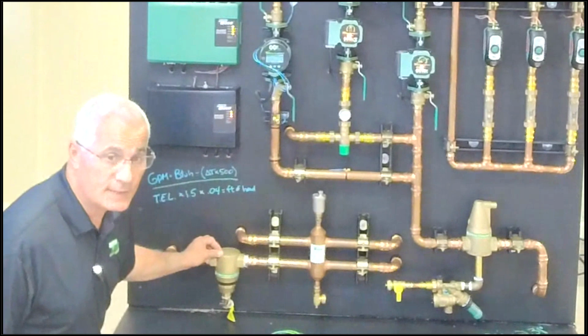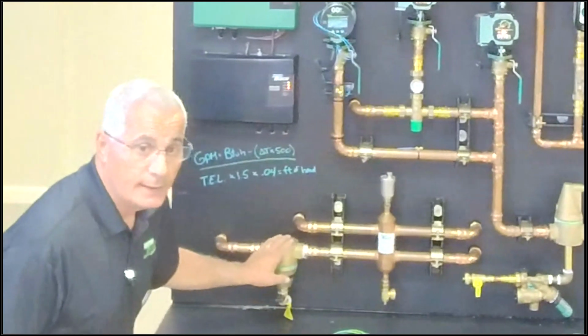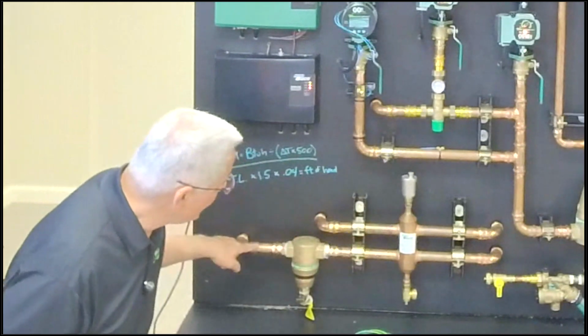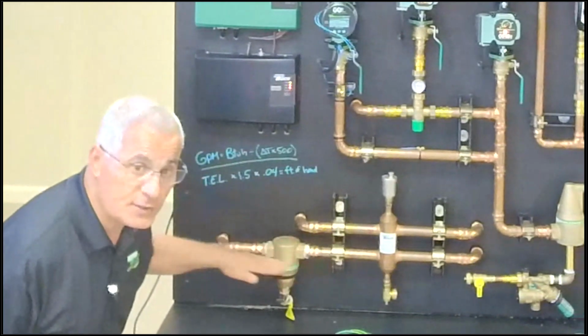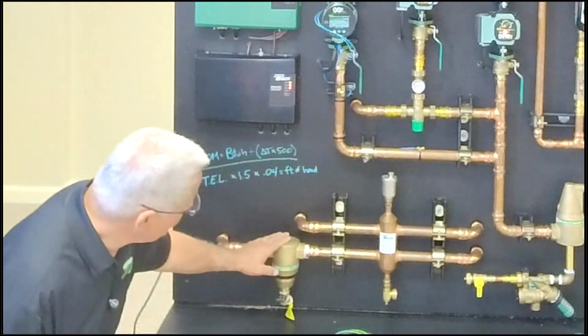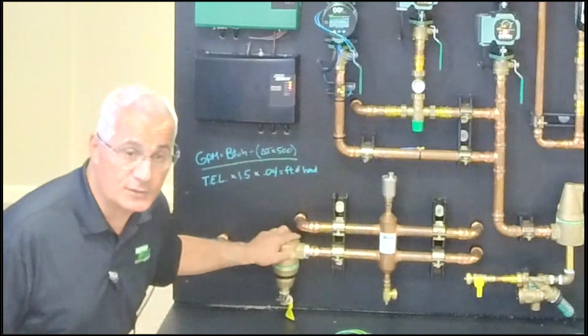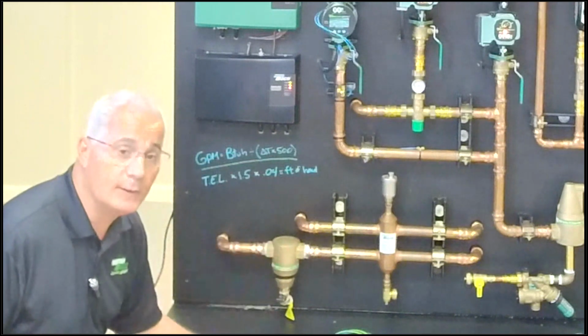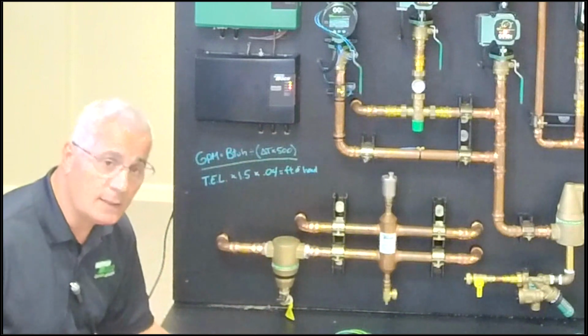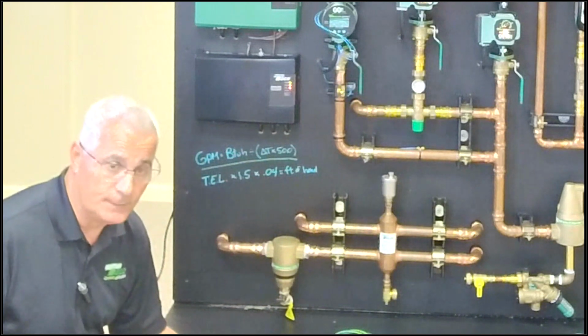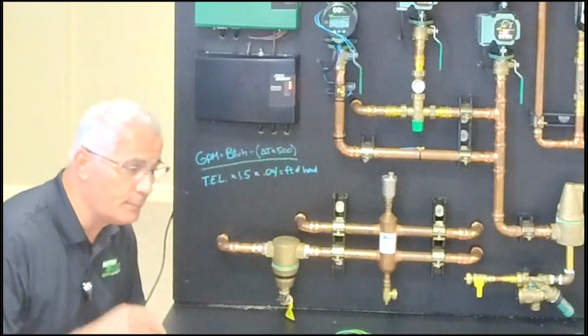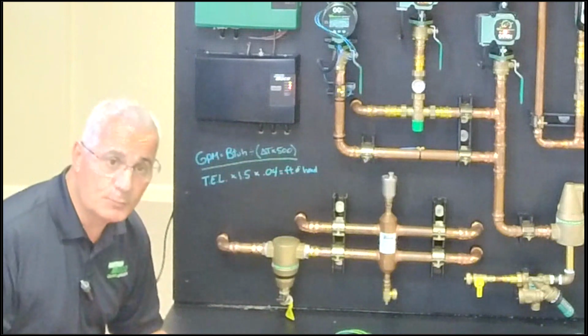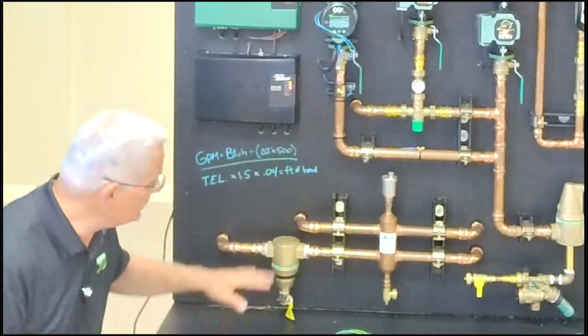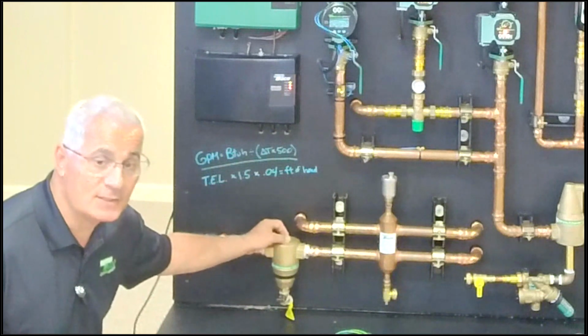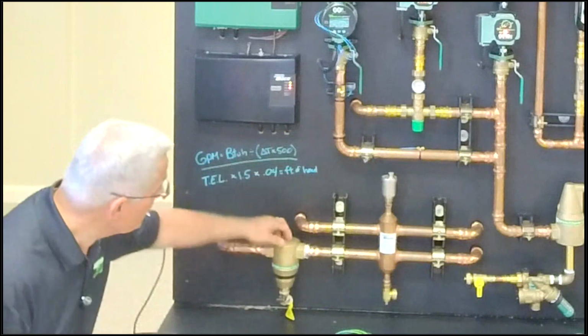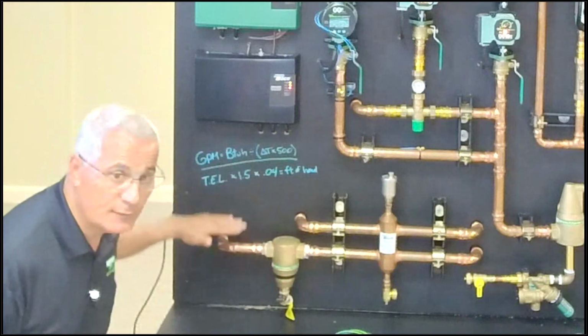If I look here down at the bottom, you'll see that on this pipe here, I have a mag dirt separator, and it's on the return side. So my flow rate from the boiler is coming this way and back. So I've got a flow rate here just for the boiler. This mag dirt separator is here to catch any debris that maybe we didn't flush out of the system and capture it here before it gets into my boiler heat exchanger. We want that on the return. I don't want it on the supply, I want it on the return. There are other manufacturers that put the air separator and the mag dirt all in one package. Nice products. In the world of Taco, we like to separate the two because, again, I want this on the return. I want to catch that stuff before it comes back into my boiler. So I've got a unique flow rate here just for the boiler.